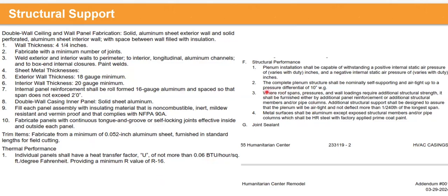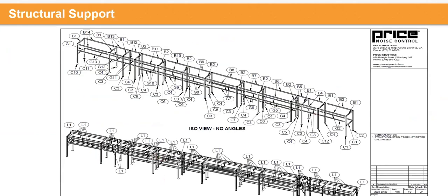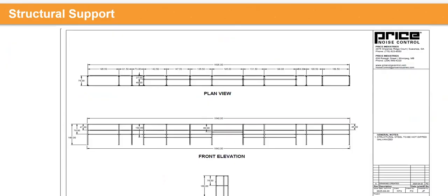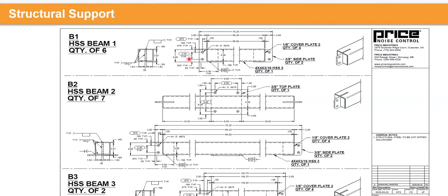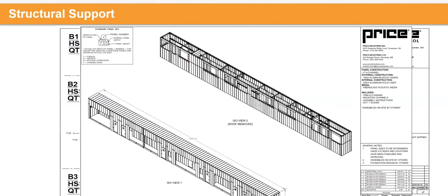Next thing you see here is that it has to be designed to 10 inches of water gauge, which is very, very high, so it would require robust structural stiffening. With structural engineering, this is what that plenum came up to with all the structural connections. We do have all the drawings, which we are able to design with the help of an external structural engineer. We have all the details, we have all the connections, and if you have something of this nature and you need to ensure there isn't condensation, then you need to take care of what the warm side conditions would be and what the cold side conditions would be. We would need to analyze that to make sure that you need or do not need the thermally broken panels. If there's a risk of condensation, then we would provide the thermally broken panels for that application.